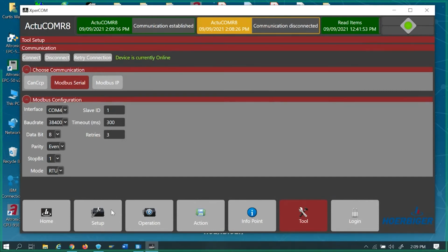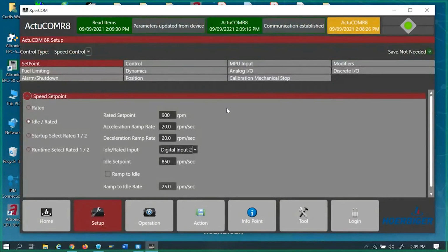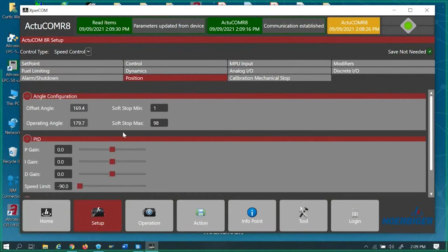I hit yes mostly because I'll get the offset numbers that are in our position, like I have an offset angle of 169.4. This number is very important. I know at first we'd always say, heck, it doesn't matter, 0, whatever. But I found that you need to put this offset number in. It's printed on top of the governor, right by the serial number. This is a number that we need to be putting in here.